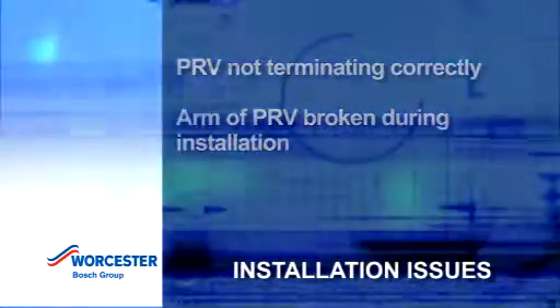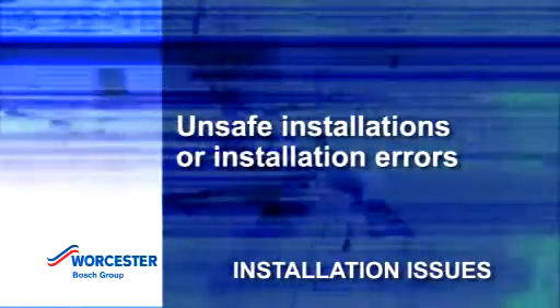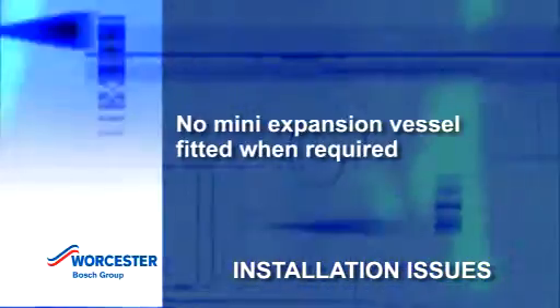The arm of the pressure relief valve broken during installation. Debris found in the diverter or flow turbine. Unsafe installation or installation errors. Combustion mixer not fully tight or the settings have been altered. And no mini expansion vessel fitted when required.